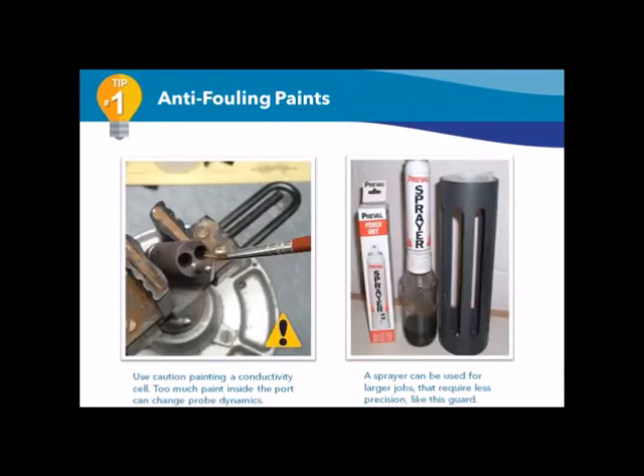Each sensor can be removed and painted separately, along with each part of the sonde, including the guard. Paint is applied in thin coats and allowed to dry, and then reapplied for maximum effect. This process needs to be repeated periodically, as the paint will flake off, or if it's removed during the cleaning process.